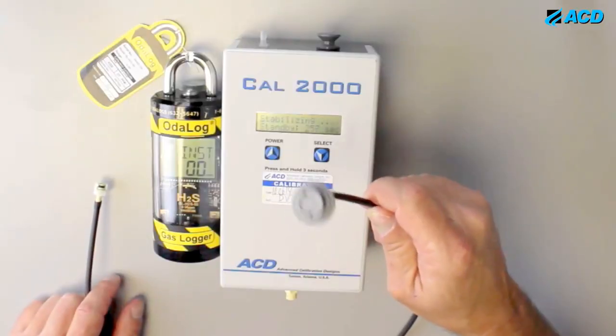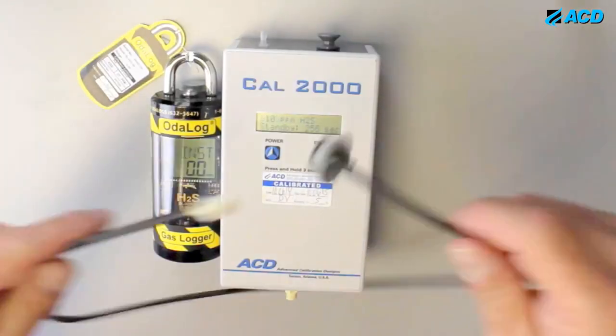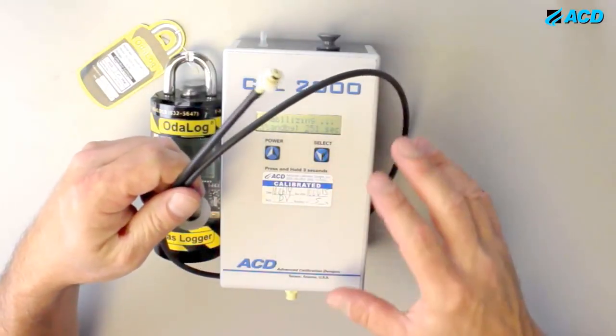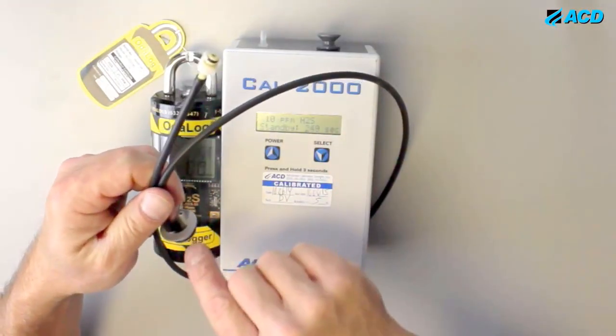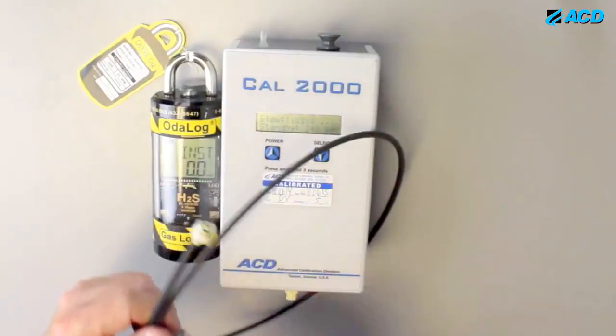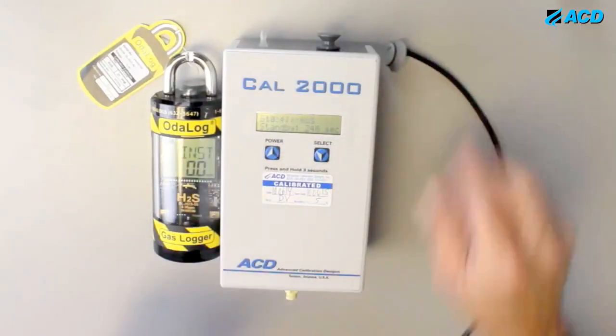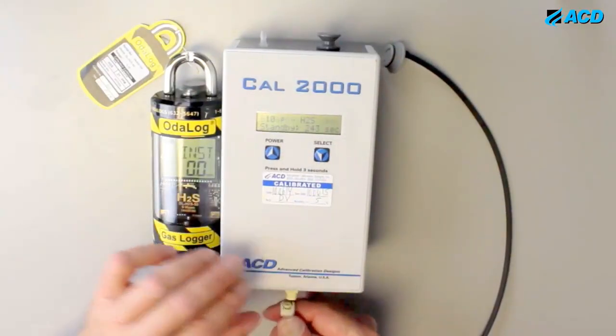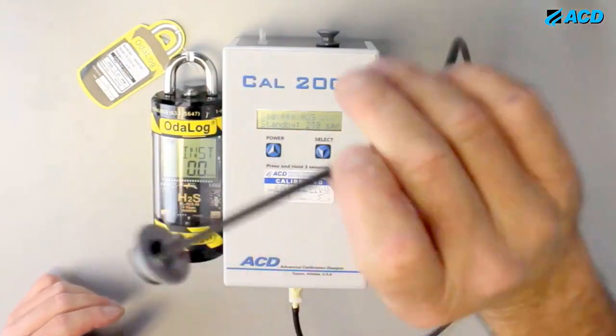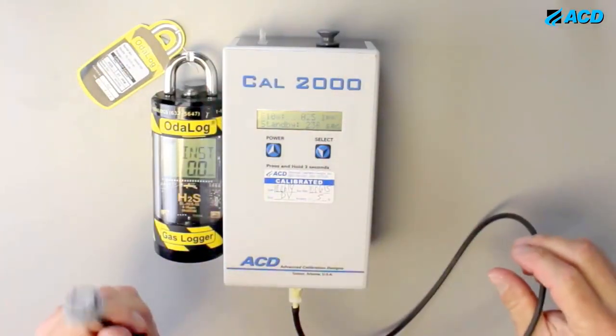OdaLog sends this calibration cup, but this applies for everybody. You can use this hose that we give you. You attach it to whatever manufacturer's calibration adapter you have, and then you can calibrate their sensor. This is a quick connect, so it's a quarter turn. Okay, the hose is on, and now there's hydrogen sulfide gas being delivered out of this.